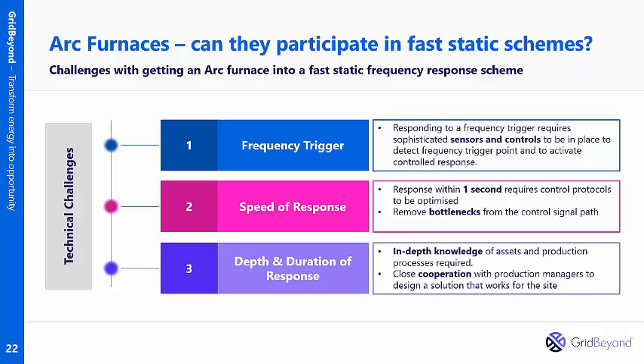What happens is we could be going through a PLC that's controlling a full site, and there might be a 3 or 4 second delay, or there could be a PLC talking to a different PLC that talks to the arc furnace. So it's about looking at the current control on site, and if it isn't good enough, coming up with a solution to deliver this 1 second response.